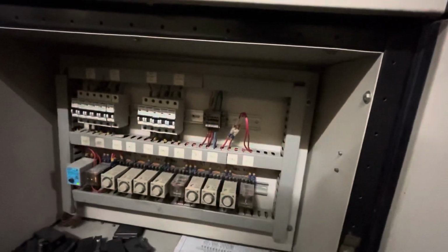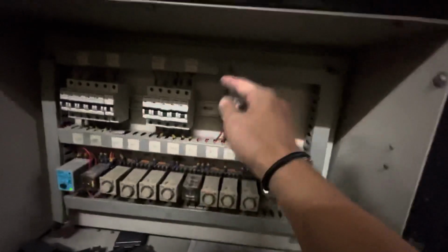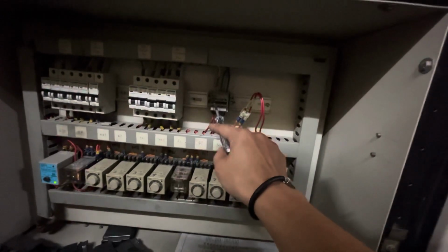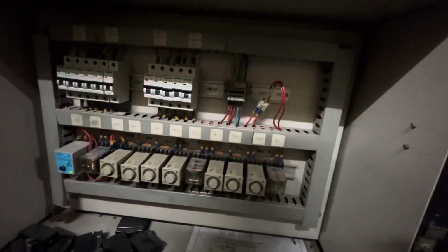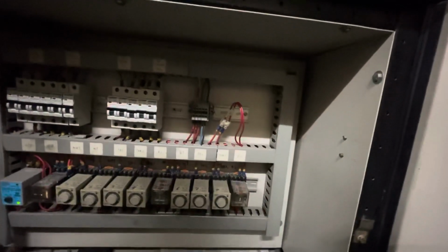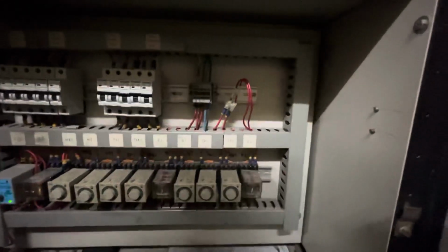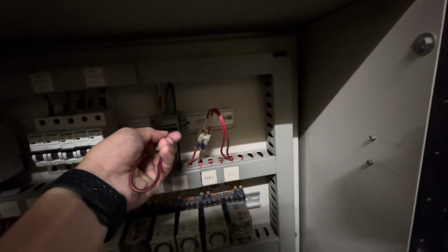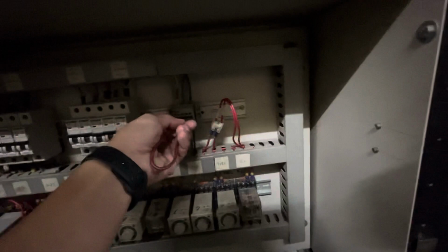Alright, I'm going to trigger the genset to run from this ATS panel by shorting these two cables, these two terminations. These two terminations are to call the genset to run remotely from the ATS panel. I mean, this is not the ATS, it's a changeover ACB, but in normal terms we always call it the ATS panel. Okay, let's do it. I'm going to jump the cable. Genset seems not able to run.